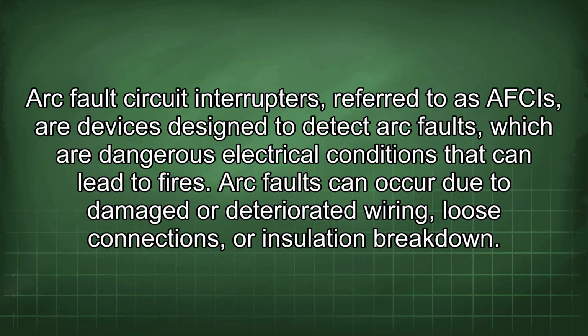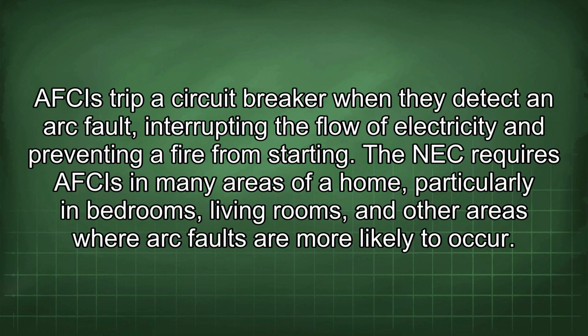Arc fault circuit interrupters, referred to as AFCIs, are devices designed to detect arc faults, which are dangerous electrical conditions that can lead to fires. Arc faults can occur due to damaged or deteriorated wiring, loose connections, or insulation breakdown. AFCIs trip a circuit breaker when they detect an arc fault, interrupting the flow of electricity and preventing a fire from starting. The NEC requires AFCIs in many areas of a home, particularly in bedrooms, living rooms, and other areas where arc faults are more likely to occur.